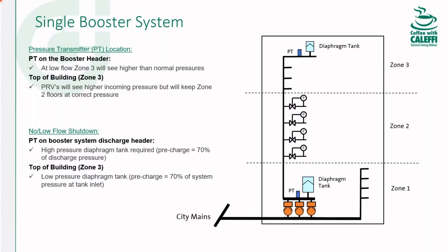That just makes the whole thing simpler, because a lot of times the location of the remote sensor isn't always optimum as specified by the designer, and then a lot more field work is involved. So you want a pump control that is easily adaptable from remote sensing to local sensing. Yeah, and for the installers and the contractors, definitely want the diaphragm tank up as high as possible, because the ASME code tanks and the high pressure tanks get pretty expensive to put down near the booster. That's a critical thing. Yes.